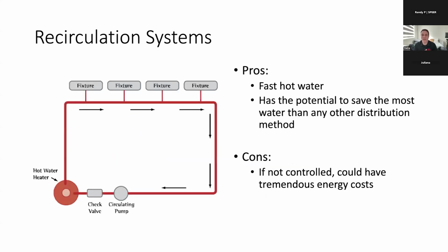Last but not least, we have hot water recirculation systems. These types of systems are becoming more and more prevalent, more popular with builders and with new home buyers. The pros is that you get fast hot water, right? You can minimize the wait time for hot water and save thousands of gallons of water per year. But if it's not done properly, these can be the most energy costly systems to operate.